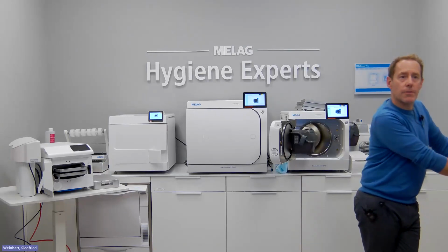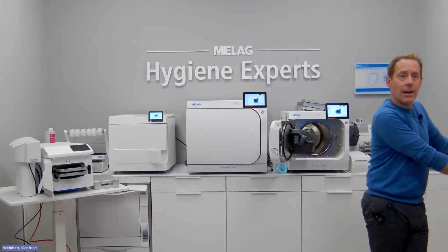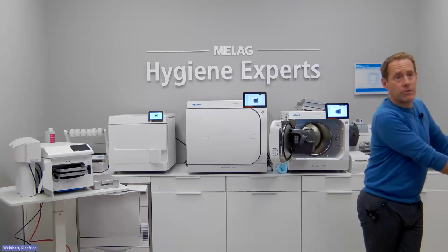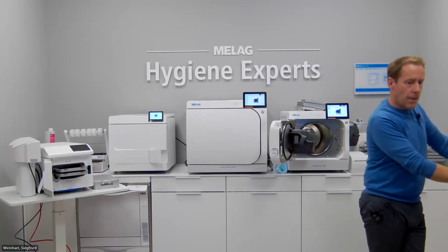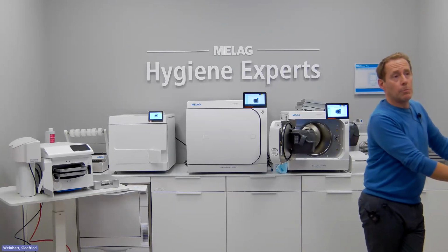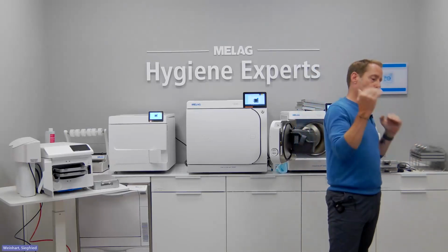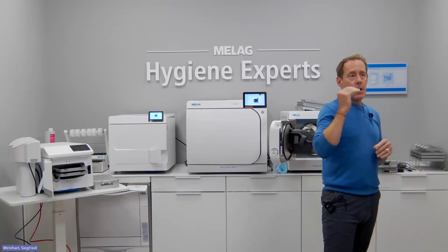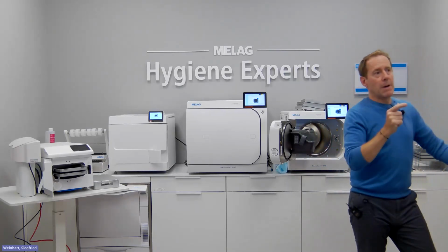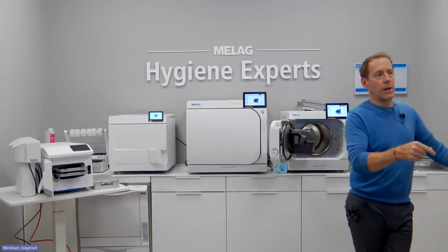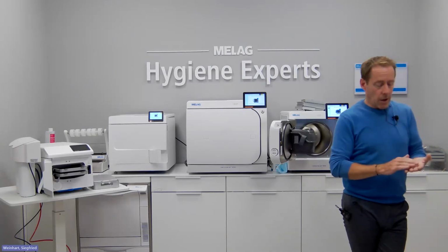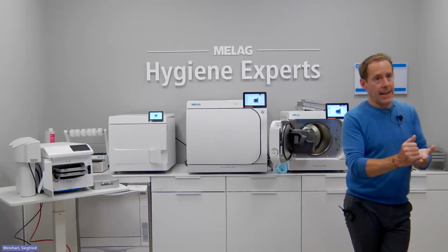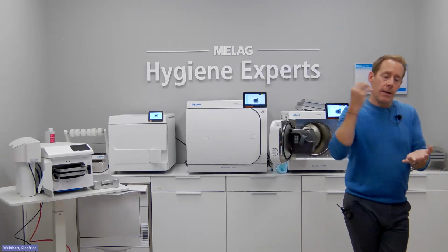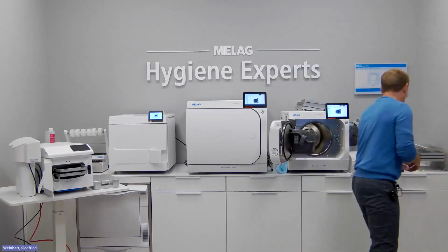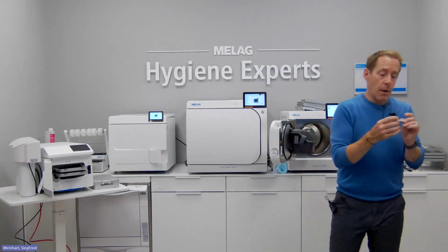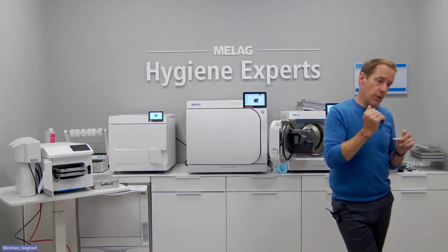Should a type 5 indicator strip be used for each batch sterilized? This is for sterilizers that don't have computer data storage. It very much depends on the unit and the manufacturer. I'd strongly recommend some form of classification be used, typically a class 6. Class 5s look at a multitude of parameters, so they are the best indicators themselves. Class 6s are cycle specific, so some manufacturers will stipulate class 6s be used on every single cycle if you don't have a data logger - purely because the class 6 will only change color when the temperature's been hit, when the time's been hit, and when the steam has penetrated the lacquer on the test strip and changed its color.